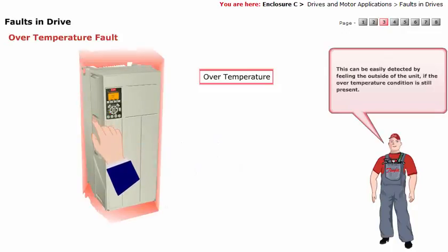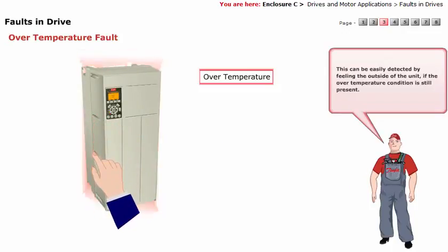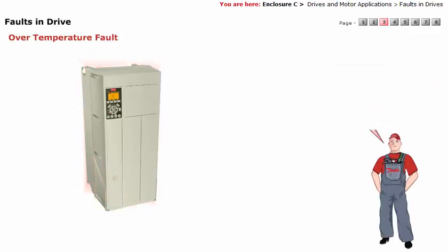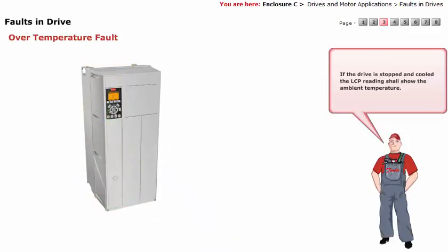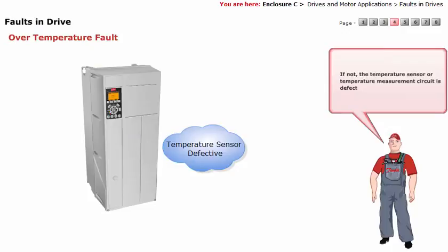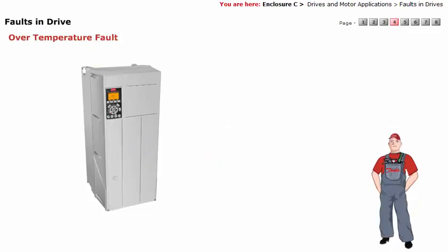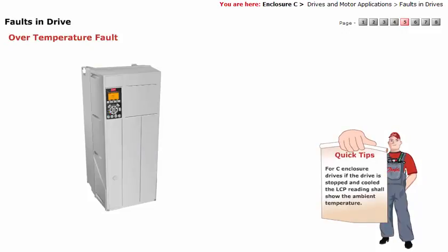This can be easily detected by feeling the outside of the unit if the over temperature condition is still present. If the drive is stopped and cooled, the LCP reading shall show the ambient temperature. If not, the temperature sensor or temperature measurement circuit is defective. For C enclosure drives, the temperature sensor must be checked using an ohmmeter. The resistance at 25 degrees Celsius shall be 10 kilo ohms.